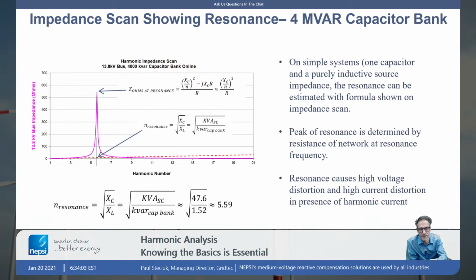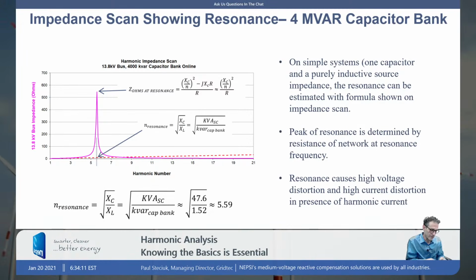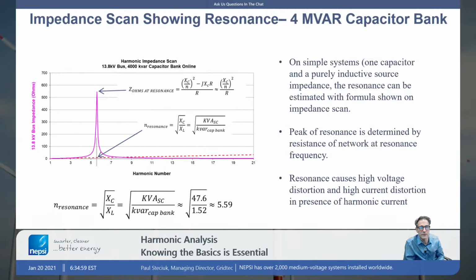1 amp of current at this frequency here would result in about 550 volts. So I can take 550, divide by 7960, which is the line to neutral voltage at the fundamental, it'd be 6.91%, so just 1 amp of current injection. And 1 amp of current injection at that 5th or near the 5th harmonic is not a lot of current injection. So resonance is something you want to avoid. The resistance of the network is always very low. So at resonance, you're going to get these peak values in your impedance, which is going to result in high voltage distortion, high current distortion. It's going to amplify the current. So you want to avoid resonant conditions where they can interfere or overlap with harmonic current injection, say at the 5th or at the 7th or at the 11th, those primary harmonic currents that you often see.